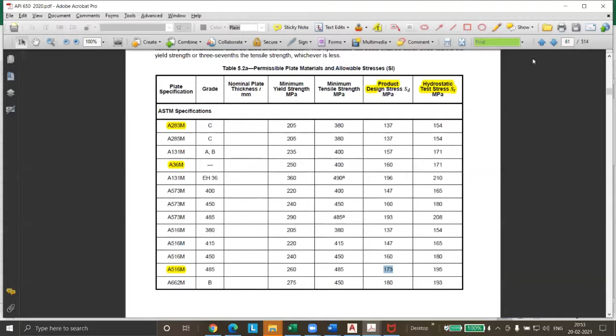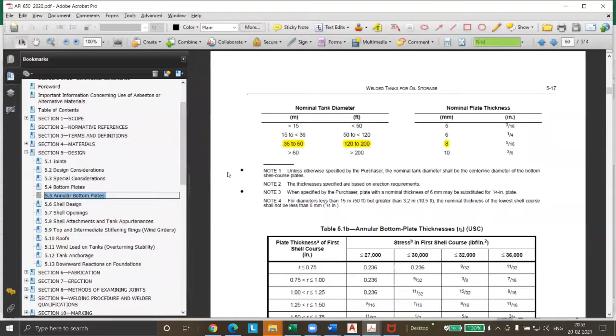Now let us read what it says for that. So when the bottom shell course is of material 4, 4A, 5 and 6 and the product stress for the first shell course is less than or equal to 160 MPa. In our case, like in A516 grade 70 case, our SD is more than this. So first it is comparing with the product stress. In the same line, it is also comparing the hydrostatic stress. If the product design stress is less than or equal to 160 MPa, or the hydrostatic test stress for the first shell course is less than or equal to 171, the lap welded bottom plates may be used in lieu of butt welded annular bottom plates.